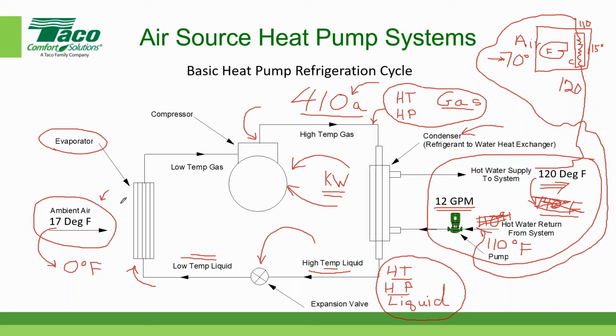Okay. So now, look at this. It leaves the evaporator. The refrigerant is now, you ready for this? It's now a low temperature, low pressure gas. I'm going to put the letters: low temperature, low pressure, and now it's a gas. It's very important that it leave the evaporator as a gas because we want it to enter the suction side of the compressor. So it's entering the compressor here as a gas.